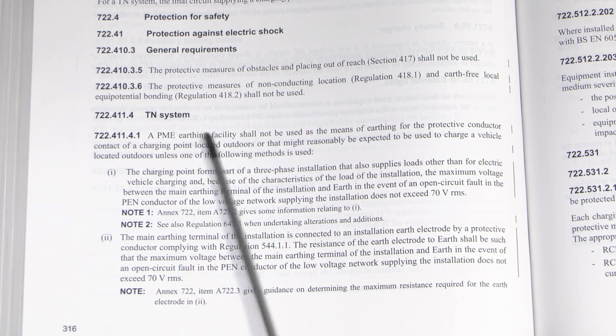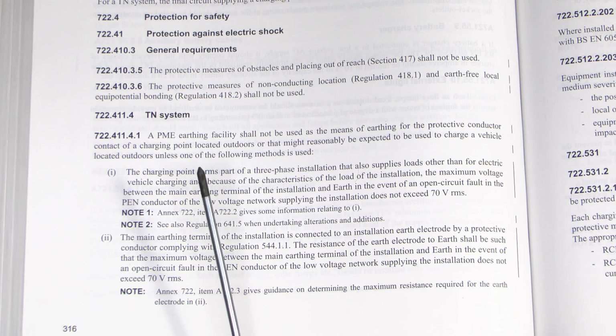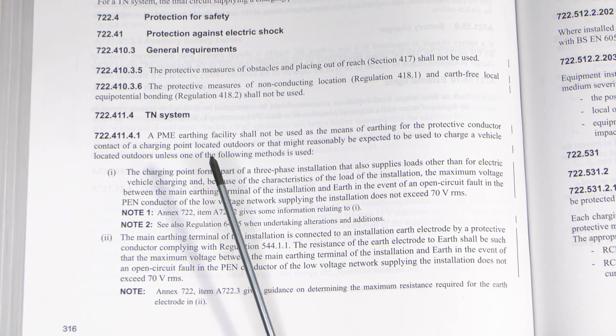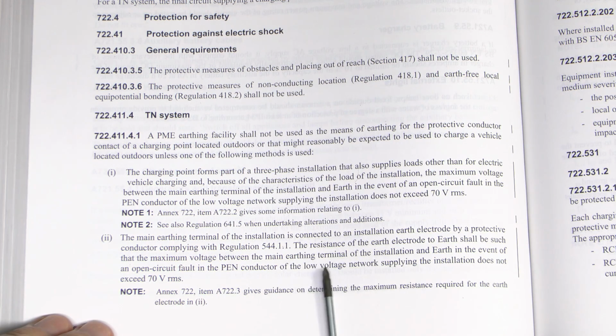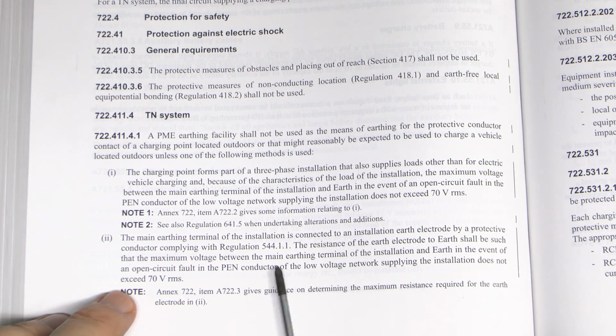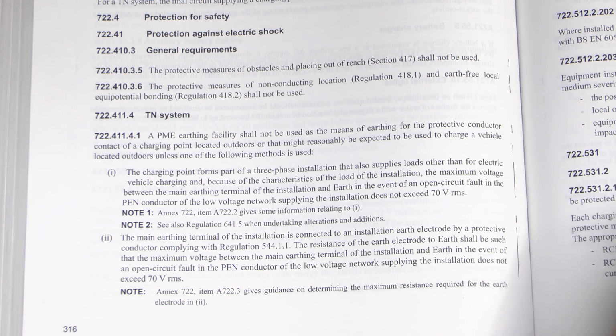So you're basically ignoring the supplier provided earth connection, not using that at all or connecting to it in any way, but you're going to put in your own earth electrode in the ground, do the recommended tests on that, and again that's all in the other part of the regulations, and then that and that only becomes the earth connection for the charging equipment. And this one here about putting in the electrode and connecting it to the earthing facility is a big fail because, as it says here, the voltage in the event of a fault between the earth electrode and the supplier's conductor must not exceed 70 volts. So let's just have a look at the calculation it gives in 722, to see why that's realistically never going to happen.